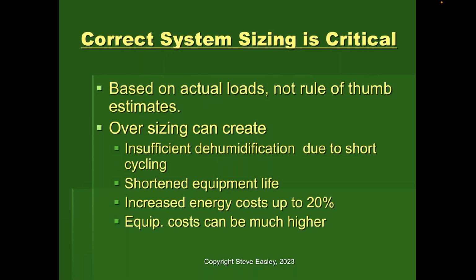System sizing is really important, and we don't use rule of thumb measurements. If somebody says you're putting a system in and it's going to be 400 square feet per ton, you need to find a new person, because you might have the same square footage as your neighbor, but your house may have double the square footage of glass that faces west. You're going to have totally different loads. That's why it's really important to size the equipment right. And the beauty of inverter-driven equipment is that, because it's computerized and based on the load, it's much more forgiving, with much less of an impact on overall performance.